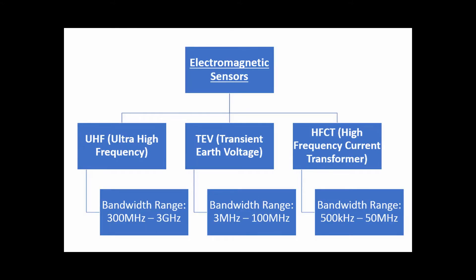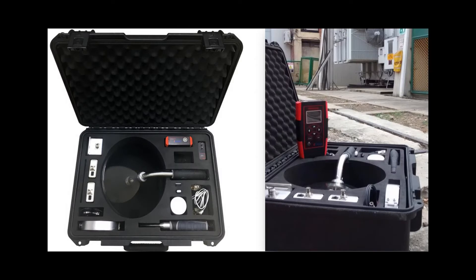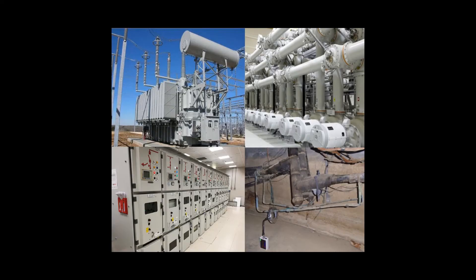The exact type of PD can be determined effectively using multiple on-screen data spectrum analysis. The P-Detector greatly simplifies and standardizes the routine online partial discharge testing procedure by using the intelligent patrol function. It is a very powerful and helpful tool for substations to quickly determine what the issue is and where it's located. The P-Detector is mainly used to test medium voltage and high voltage switchgear, transformers, power cables, and GIS.